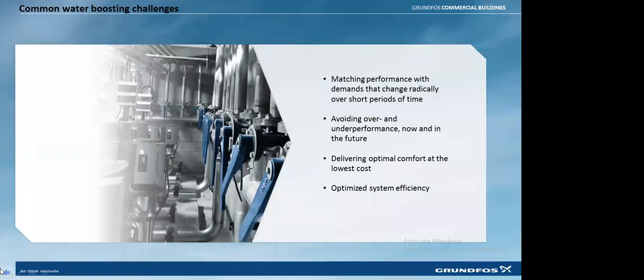Then again, sometimes we may not get optimal comfort. Maybe we will have certain issues with hot water, cold water mixing. Some of the basic issues: the pressure will be very low, or the systems are running continuously. These are some of the common running issues on the hydro-pneumatic system. Another overall aspect is efficiency. Overall, our intention is to ensure that systems run at a better efficiency point.